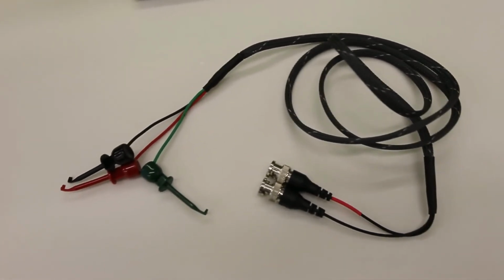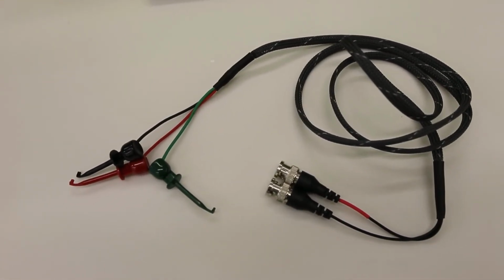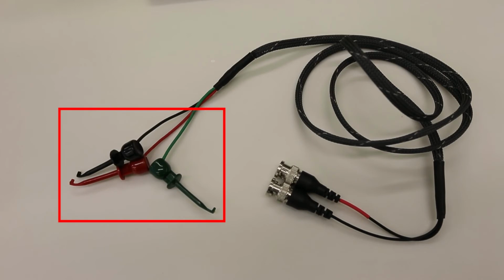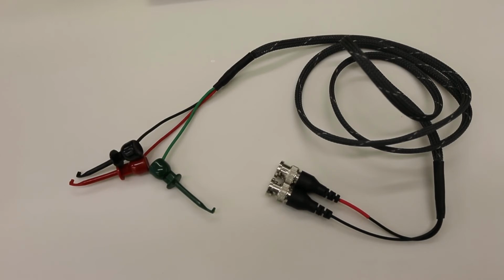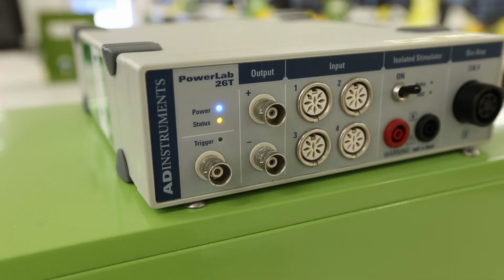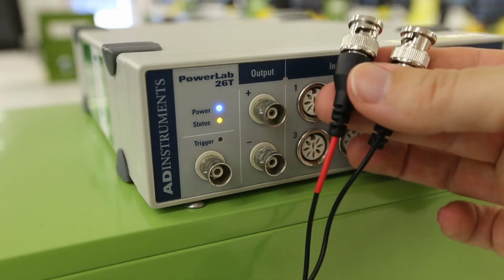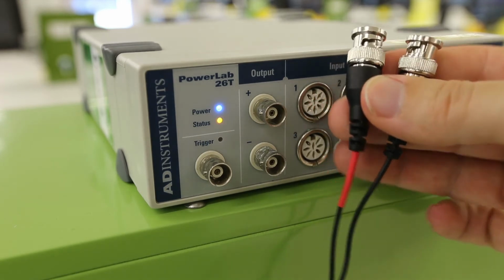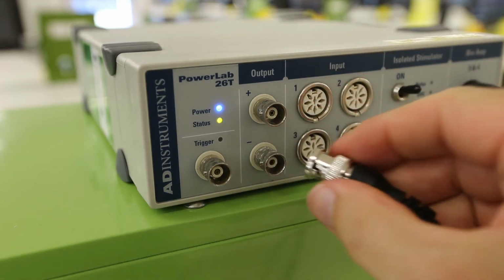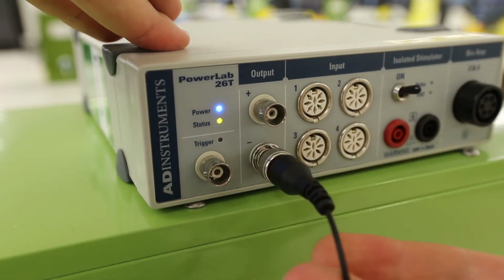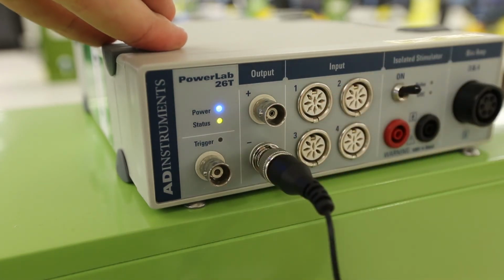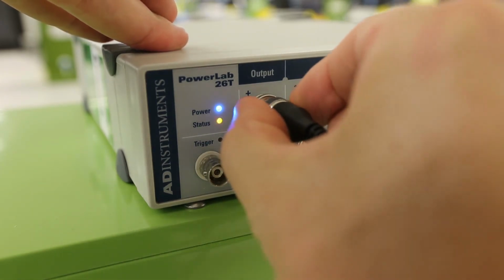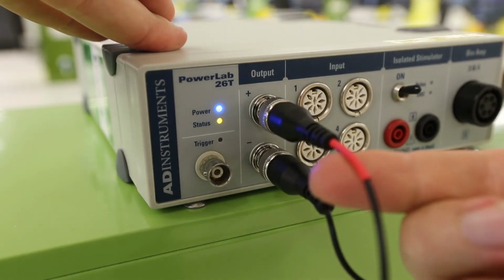We can now attach the muscle stimulating electrodes. These are the ones with the hook electrodes down one end. The connectors down the other end of this cable are called BNC connectors. Attach the BNC connectors to the output terminals of the PowerLab. You attach BNC connectors by plugging them in and then turning the collar clockwise. You should attach the black electrode to the negative terminal and the red electrode to the positive terminal.